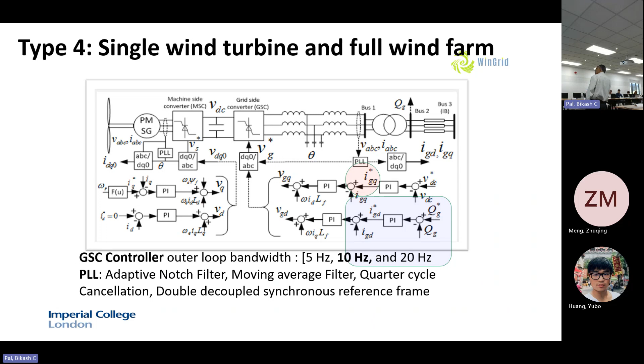Everybody knows this. So the controller for the grid side converter, bandwidth will vary between 5 to 20 hertz. And the PLL, the phase lock loop technologies, we used actually 4 or 5 technologies like adaptive notch filter, moving average filter, quarter cycle cancellation, and double decoupled synchronous reference frame. So these 4 types of PLL, we put here, and then we see what happens.